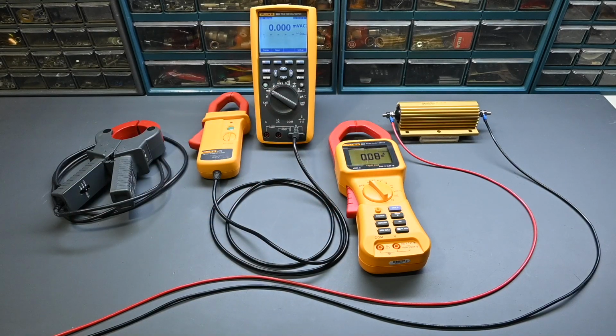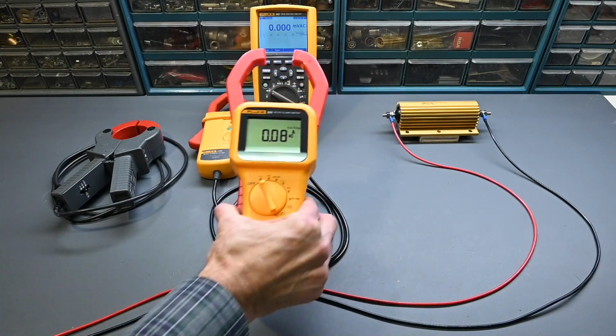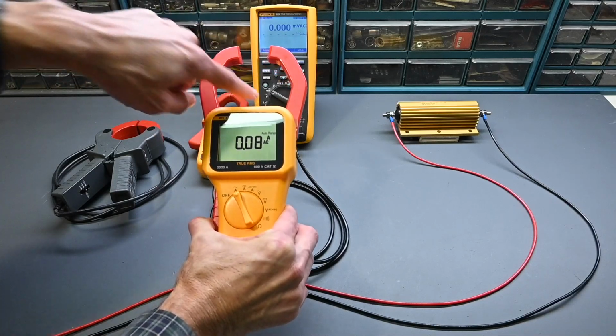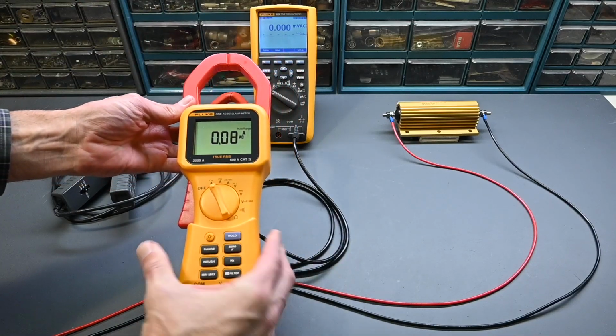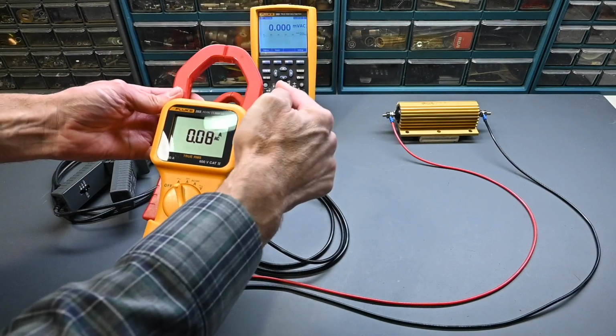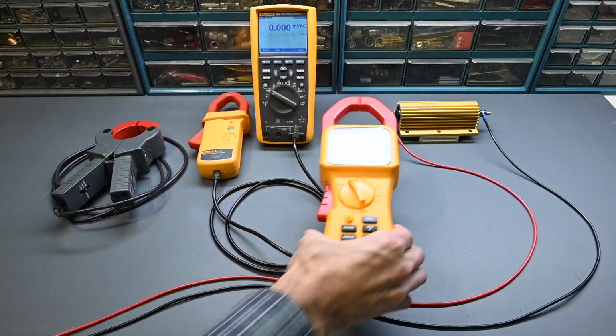Now a trick that you can do is to increase the sensitivity of the current clamp by looping the wire through the jaws of the clamp. So as I mentioned, you would open the clamp, you put the wire in here, and it just passes straight through, and that's how they're intended to work normally. But if you take the wire and you add a loop, it will double the reading. We'll take a look at that in just a moment.